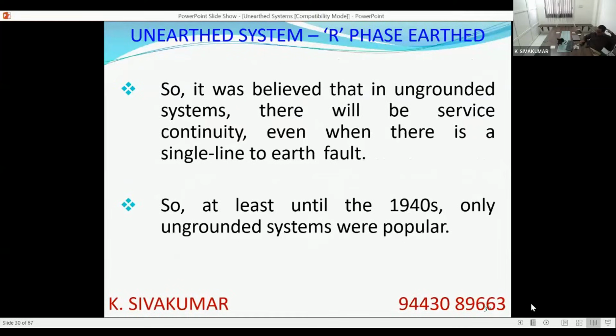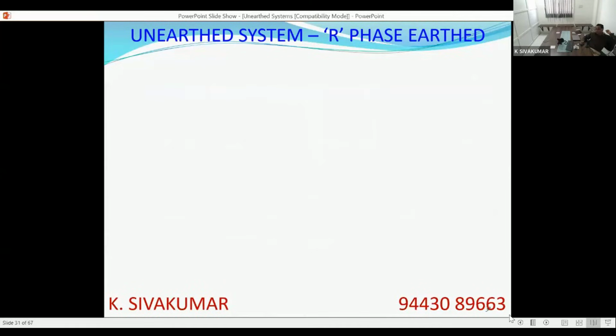The other day I was seeing a reference to some technical publications of Schneider Electric. In them, there is a book on the evolution of earthing. That also very clearly says that up to the 1940s, these unearthed systems were very popular. But then, if it is so advantageous, that there is no shock risk, earth fault currents are not very high, and there will be service continuity, in spite of all these things, we do not practice unearthed systems at all. We are much more familiar with earthed systems. So there must be some disadvantage in the unearthed system. Let us discuss the disadvantages of the unearthed system.